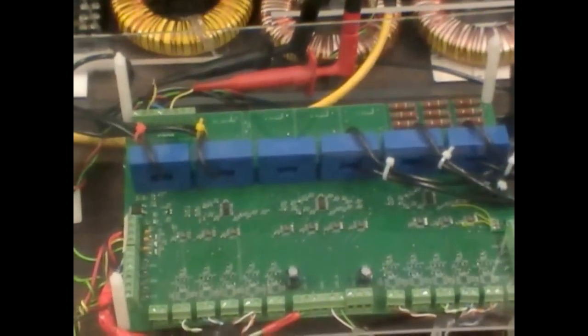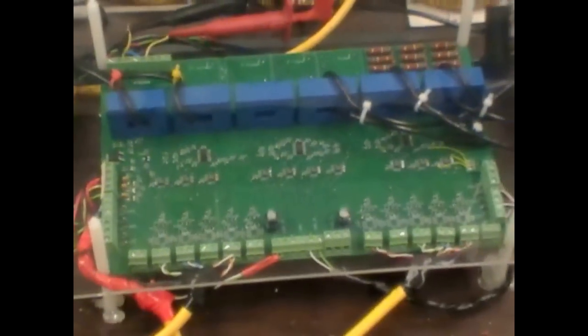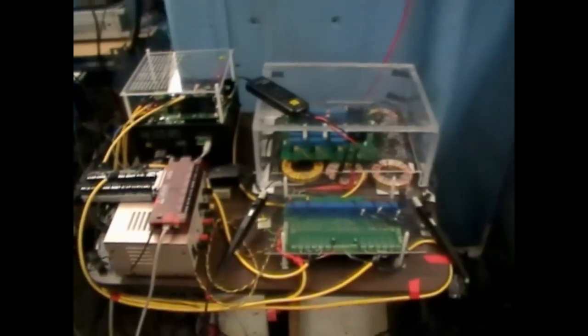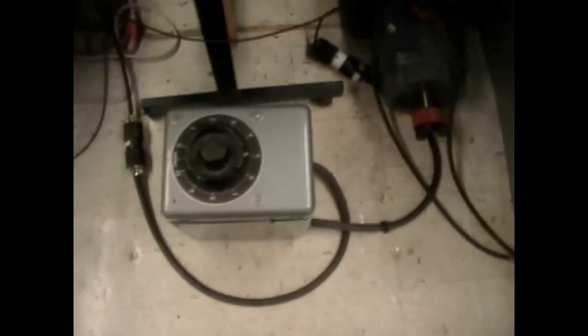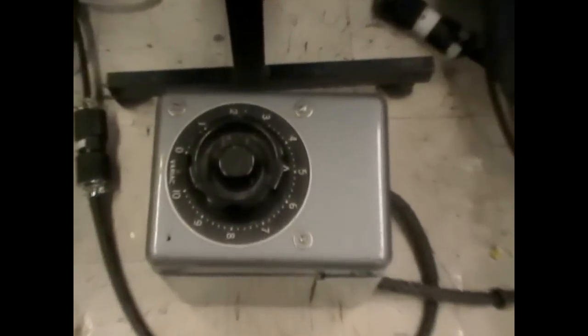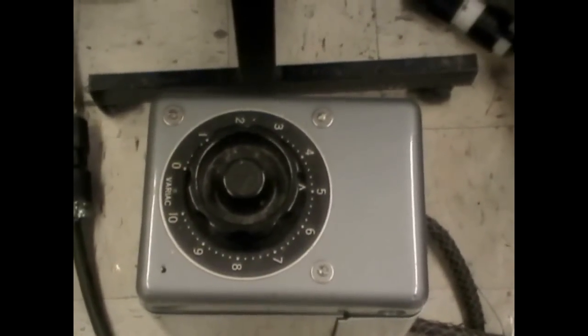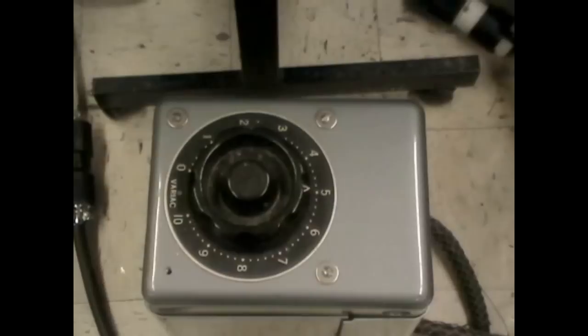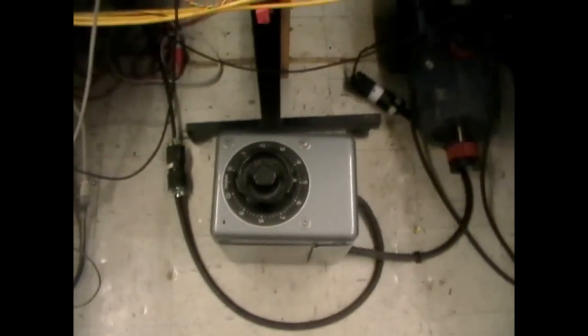Similar to the drive-in side, we have a current measurement unit here also, which measures the grid side and the inverter side currents as well as the voltages of the grid that is required for the control of the grid side converter. And the input to the grid side filter comes from this auto transformer. This is almost like a fixed transformer. We don't change the turns after the initial design. So this just isolates and gives a proper voltage to the front-end converter.